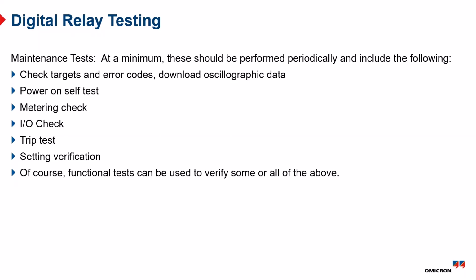And these maintenance tests have to absolutely be done. The good thing is on a digital relay, the maintenance test is a bit simpler. We check to make sure the relay powers up, download any error codes, download the oscillography, do a metering check, IO check, make sure the output contact trips, verify the settings, and of course you can do some of those with functional tests, or do additional function tests depending on what your test plan is.